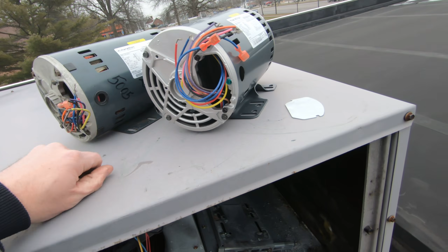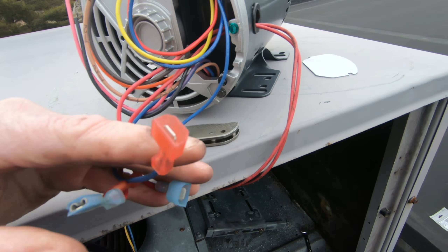All right guys, I got my 2 red wires pulled in. Now these are your thermal limit. So if the motor gets too hot, it's gonna open it up and it's gonna open that limit up. So basically your 2 red wires are gonna connect, they have a stake-on connection on them.